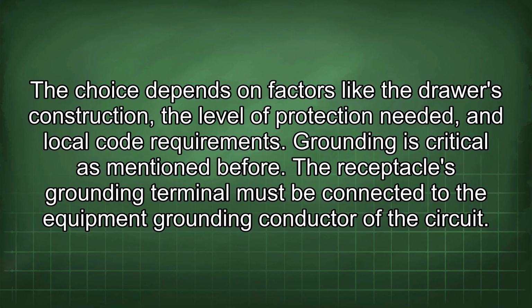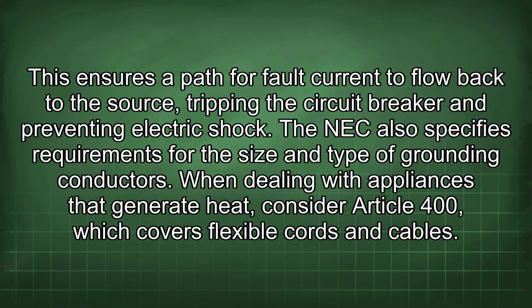Grounding is critical as mentioned before. The receptacle's grounding terminal must be connected to the equipment grounding conductor of the circuit. This ensures a path for fault current to flow back to the source, tripping the circuit breaker and preventing electric shock. The NEC also specifies requirements for the size and type of grounding conductors.